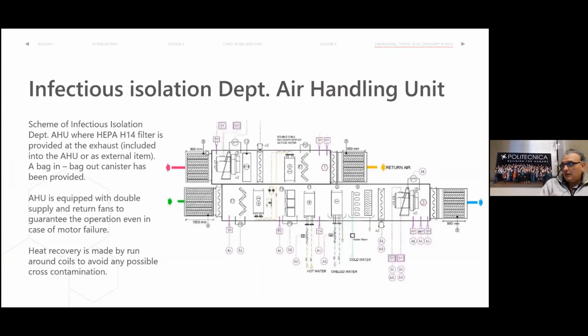This is a typical air handling unit that is utilized for an infection isolation department. Of course, we must provide a unit for this department and only for this department. The air handling unit cannot be in common with other departments. We must absolutely avoid that, because there could be some mixing phenomena or some air that moves to other unprotected areas where there is no procedure to protect the patient. And so it could be very dangerous if you use the same unit for isolation and for the normal wards, for example. So you must dedicate a special unit for the isolation department. And this is the case. It is always in this way.